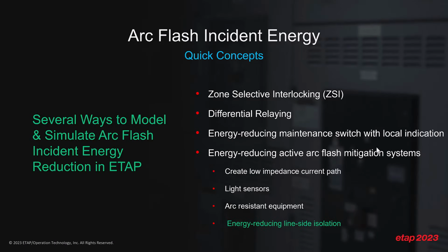Let's get to one more quick concept, which is arc flash incident energy. And of course, my goal is not to give you a full concept into arc flash analysis, but there are several ways to model and simulate arc flash incident energy reduction techniques in ETAP. There is zone selective interlocking, differential relaying, energy reducing maintenance switch, energy reducing active arc flash mitigation systems, such as creating a low impedance current path, light sensors using optical fibers, arc resistant equipment, and of course, now more recently in ETAP 2023, energy reducing line side isolation.